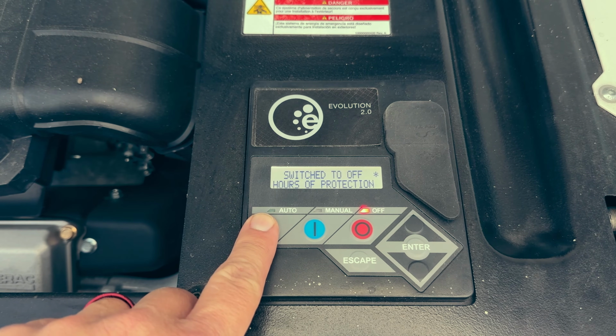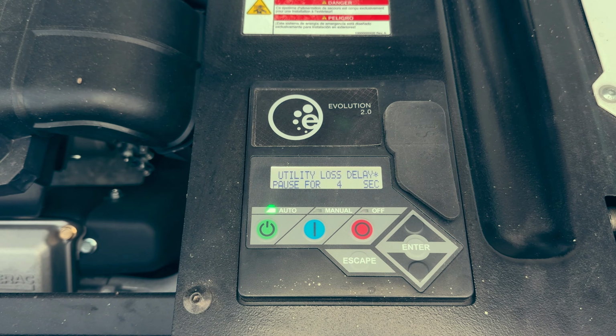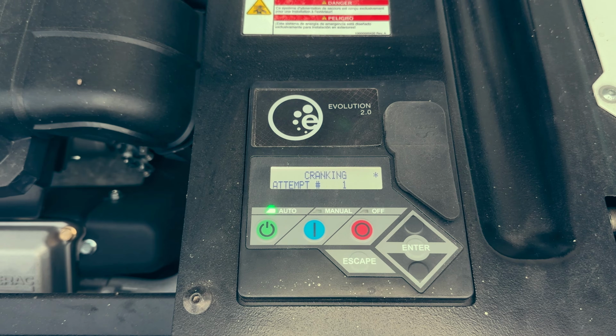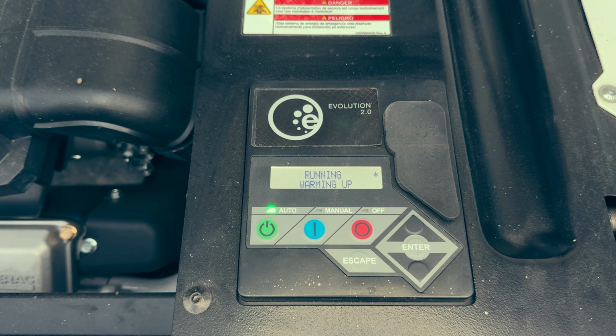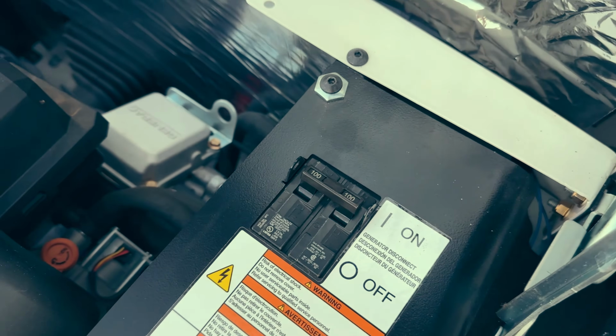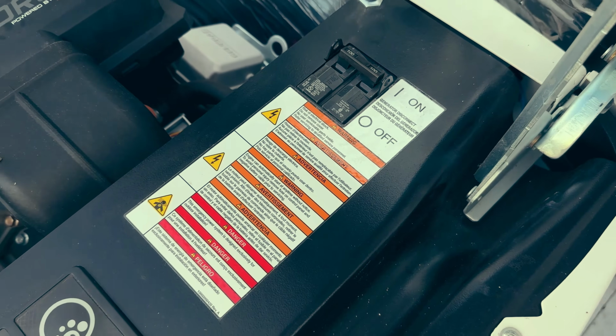Head back to the generator, press the green auto button, and watch the LCD screen. It should say utility loss and start counting down. Once the generator fires up, the automatic LED should flash in 1-second intervals. With the generator running, go back to the main breaker and flip it on. You should hear a slight pitch change in the engine, and that's the generator taking on the load.